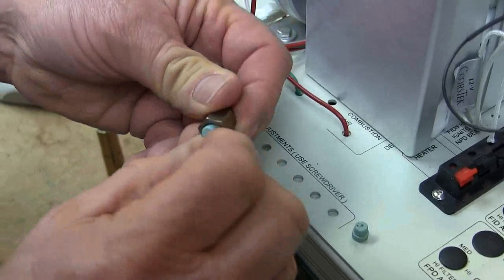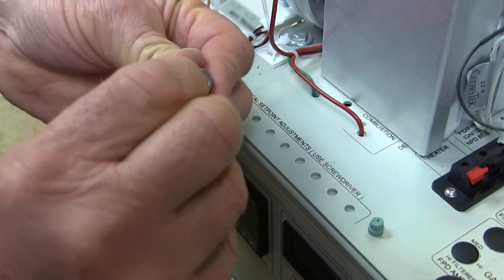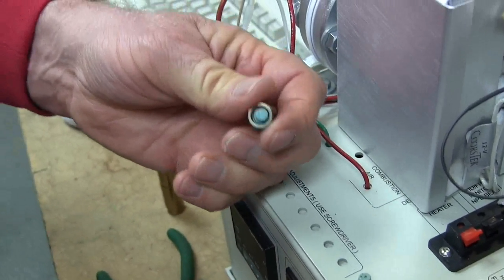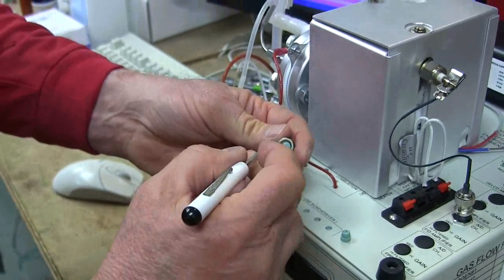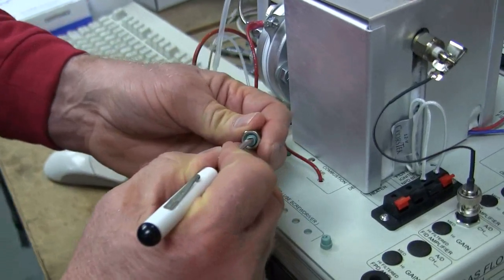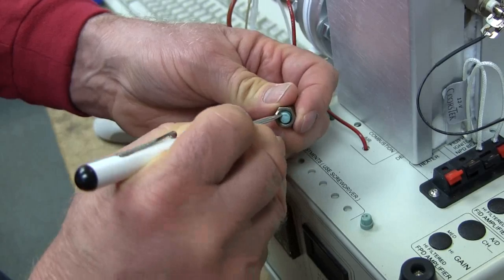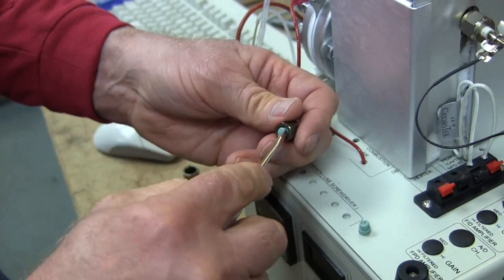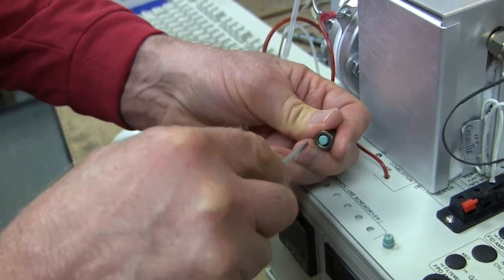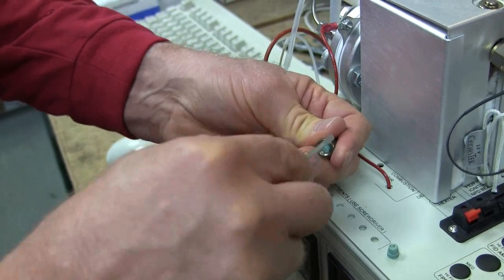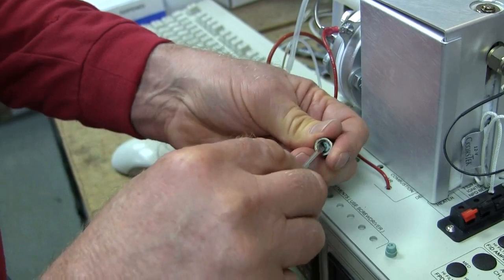It's a little bit counterintuitive, but that's how it works because the septum needs to seal against the corresponding fitting that it's up against. So you have to kind of coax the septum into the nut. I have a little screwdriver here and I'm just kind of pushing on one side or the other and coaxing it into the nut so that it sits in there kind of like that.